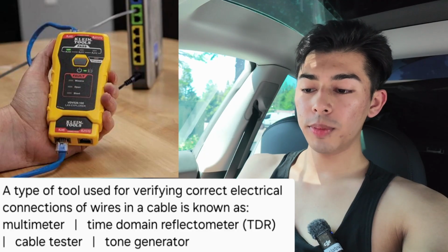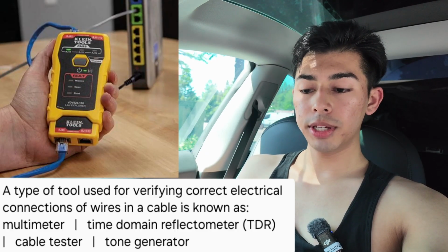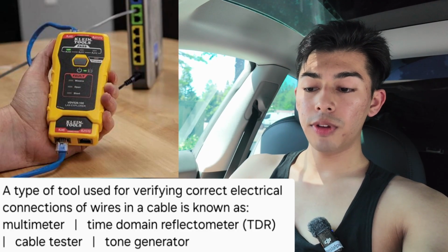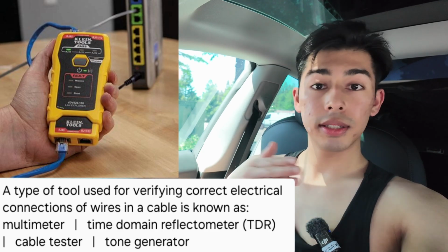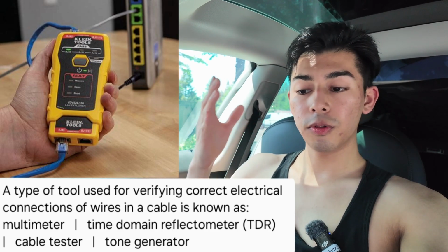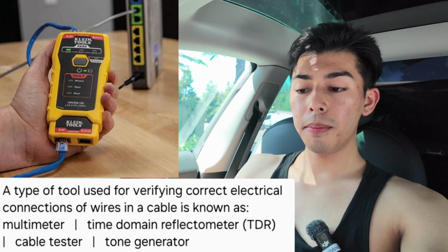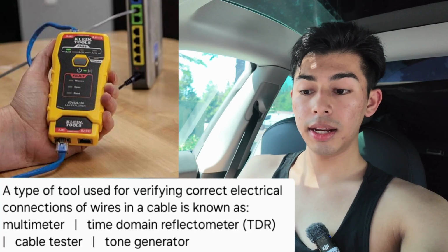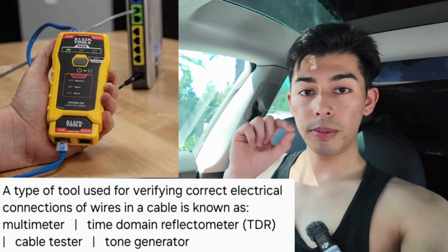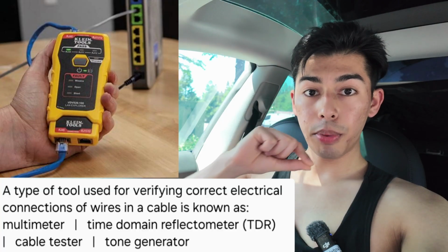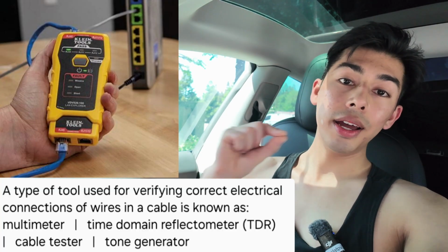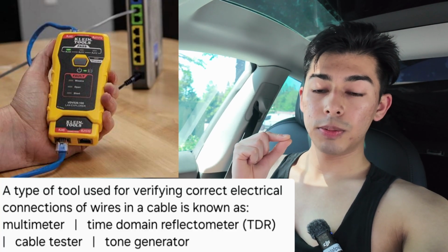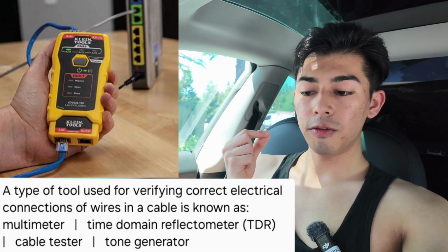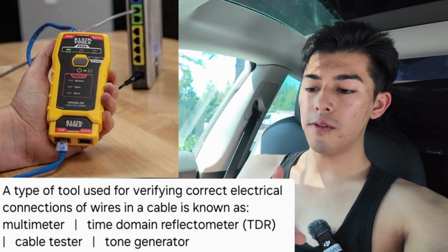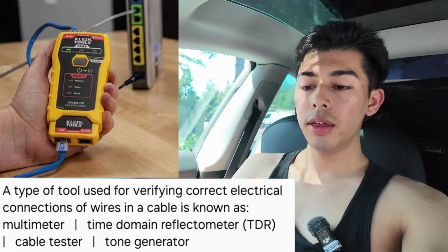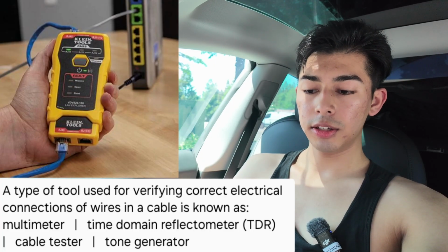Now we have time domain reflector and we have a cable tester. A time domain reflector reflects a signal. It basically looks for faults, breaks, or impedance mismatches in cables. From the part that you connect it, it'll send a pulse, and it will analyze that reflected signal. Its purpose is to locate the fault, but it's not to verify correct electrical signals. That goes to a cable tester.